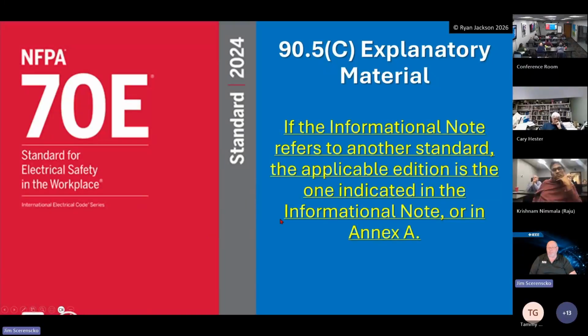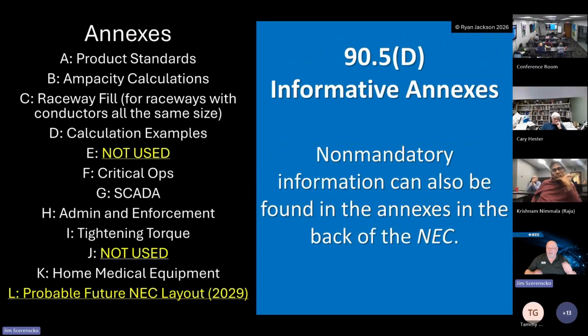70E, which is the electrical safety in the workplace code book. You know, it's an informational note or an Annex A. If it's referenced in the standard, it is going to be the current version unless it references a specific version. Okay. All annexes are informational. So that little engineer's design for duct banks that used to be in 310, they had those little pictures in there for the longest time. That was never code either. And if you look now, it's back in Annex B. And then there's that whole calculation in there for designing the duct banks, and how things in the middle, which retain more heat, have less ampacity than things on the outside and all that other stuff. That's never been code either. That's all informational purposes.